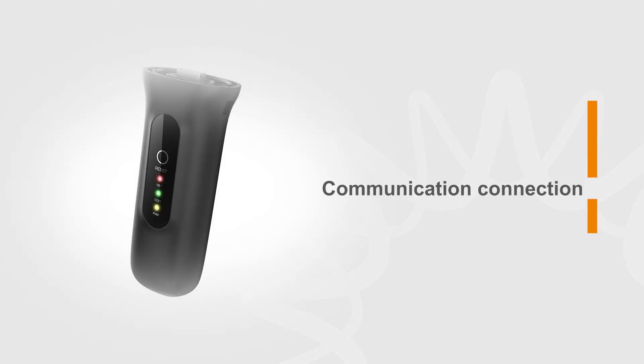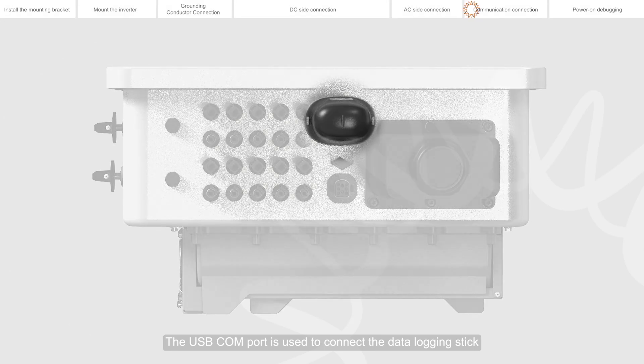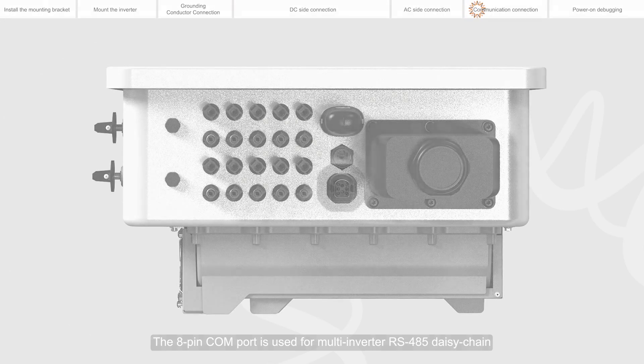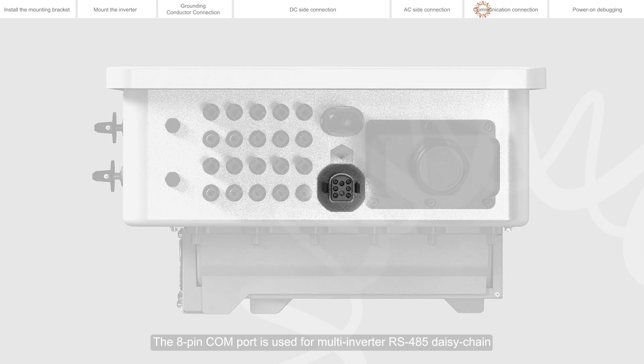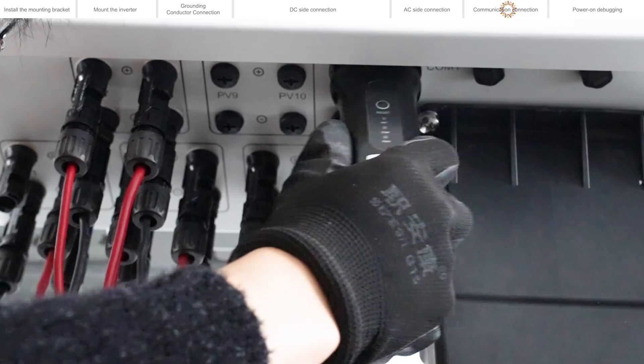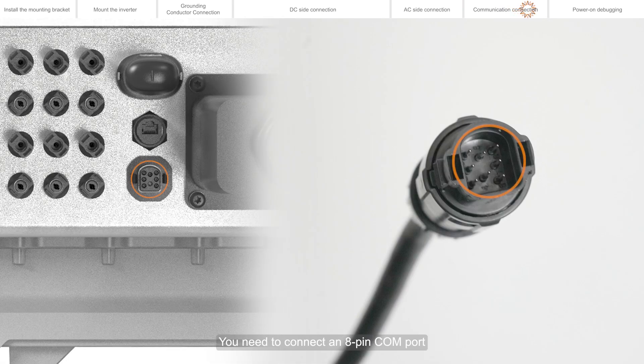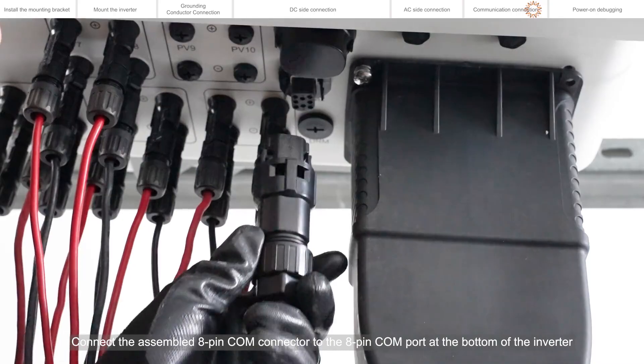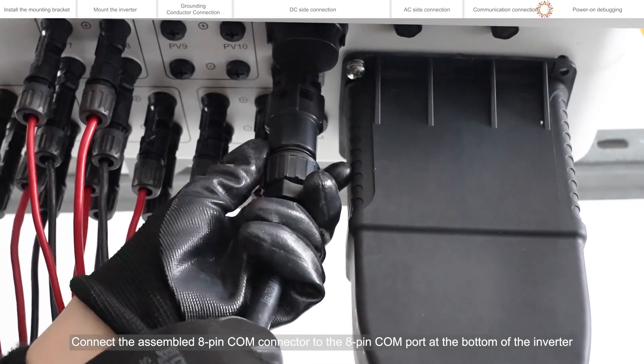Communication connection. The USB COM port is used to connect the data logging stick. The 8-pin COM port is used for multi-inverter RS-485 daisy chain connection, logic interface connection, or meter communication interface. If you choose the Ginlong Solis Datalogger, please connect it to the COM port at the bottom of the inverter. If there are multiple inverters, you need to connect an 8-pin COM port. Connect the assembled 8-pin COM connector to the 8-pin COM port at the bottom of the inverter.